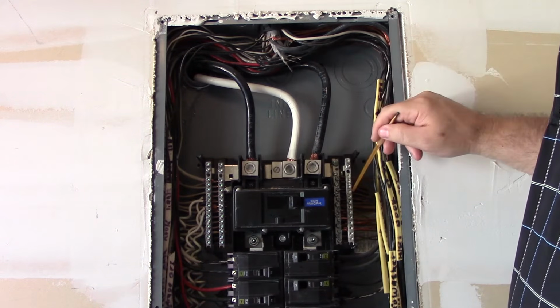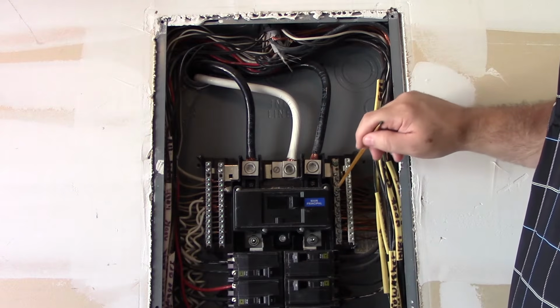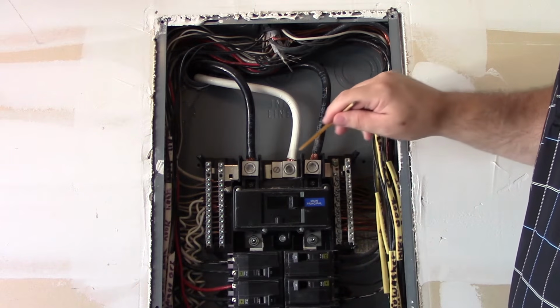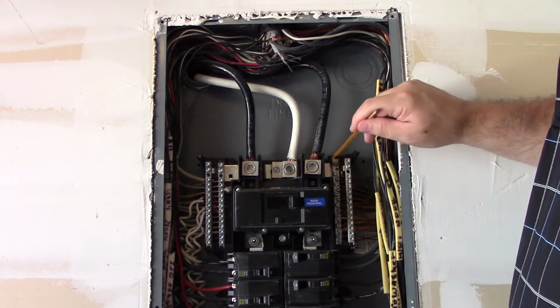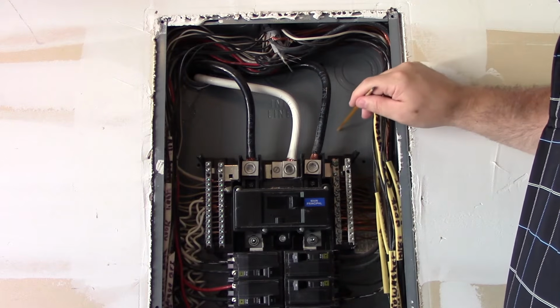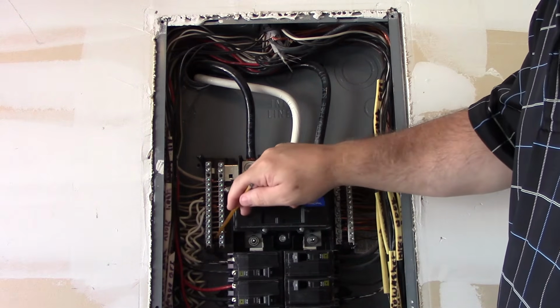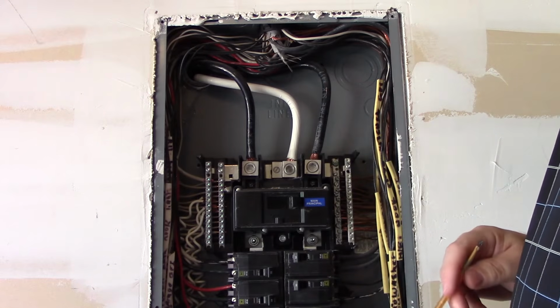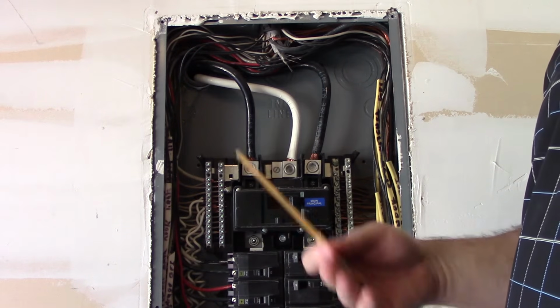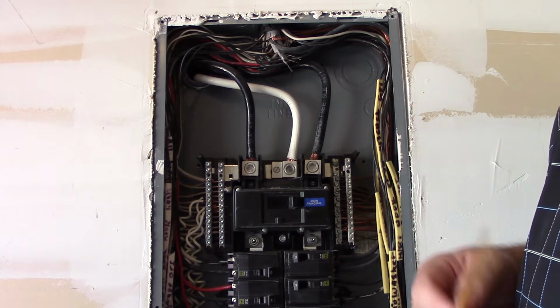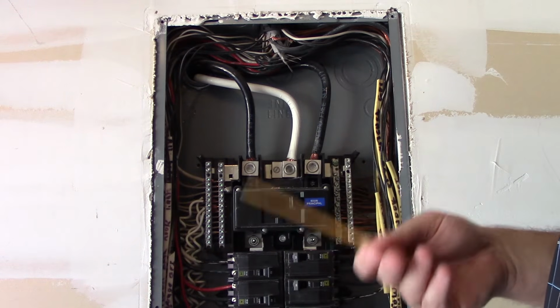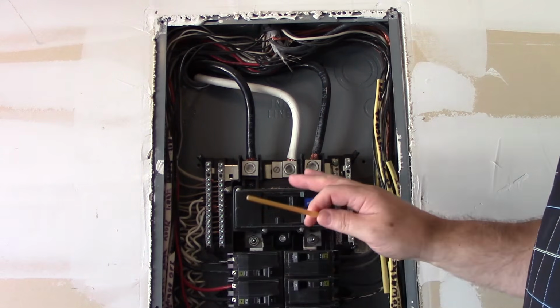The grounded conductors are connected to the bar, which is connected to the grounded conductor, which has a main bonding jumper connected to the metal enclosure. And of course, the grounded conductors over here are terminated. Okay, so now, if this was a remote distribution panel, because I get that question a lot. So let's say this is a panel that's out in your basement, remote from this one.